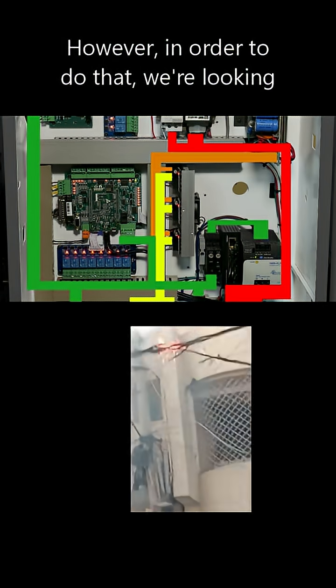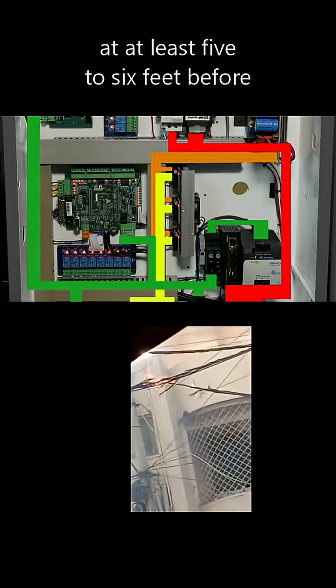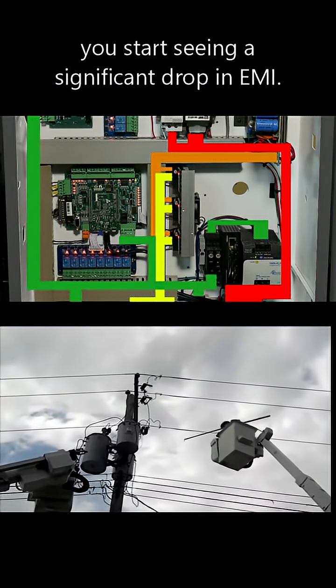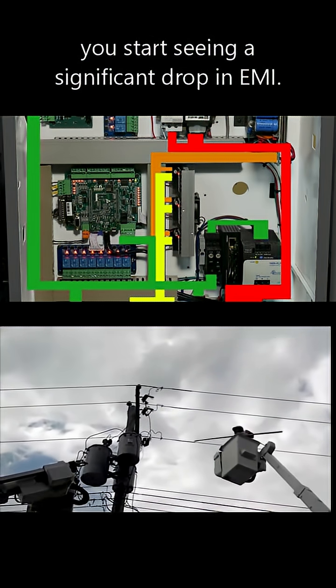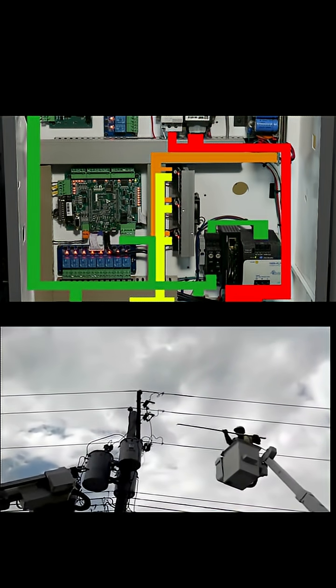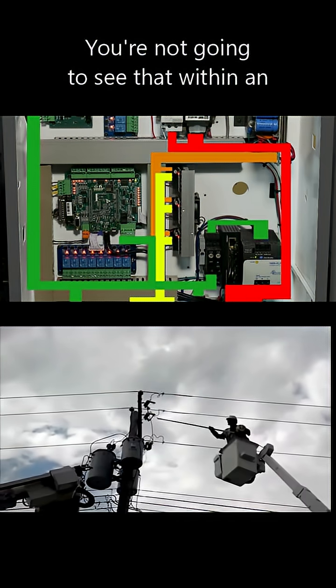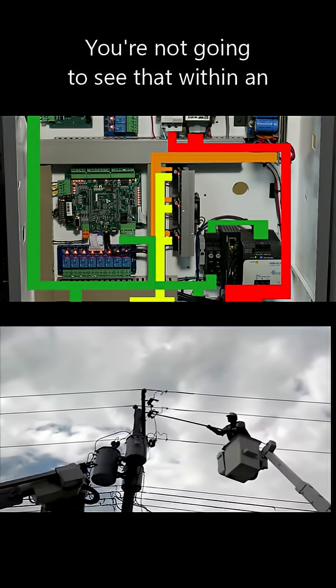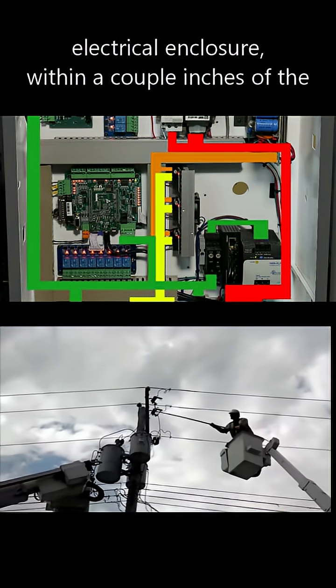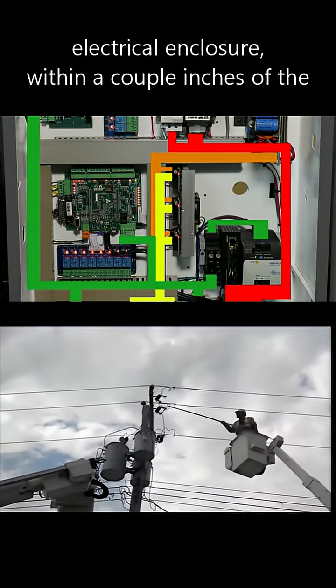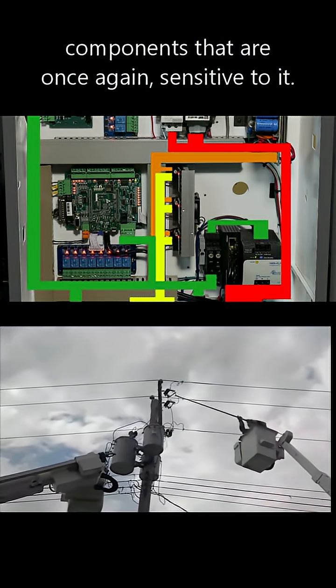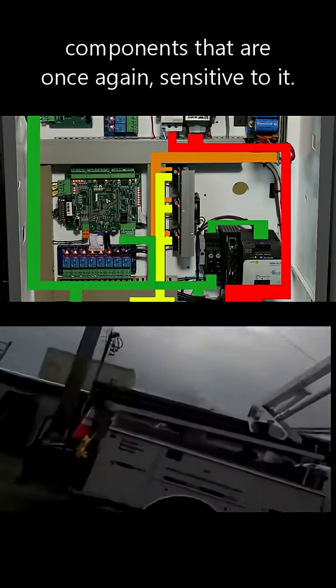we're looking at at least five to six feet before you start seeing a significant drop in EMI. You're not going to see that within an electrical enclosure within a couple inches of the components that are sensitive to it.